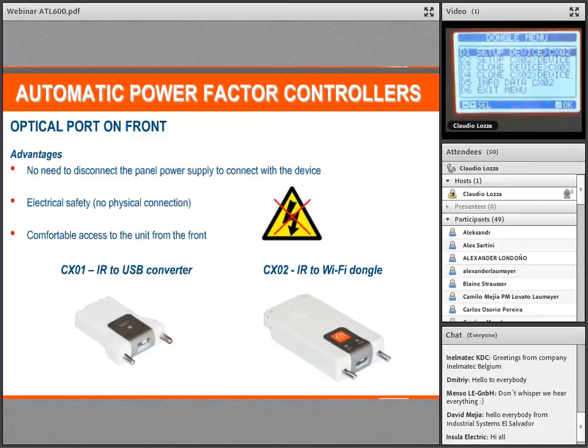Here I can, for example, with the command D1, copy the setup from the device to the CX02. Then with the second command, I can copy the setup from CX02 to the device, and then another big function, the clone function. With the command D3, I can clone the device. What does clone mean? That I copy not only the setup, but the information regarding statistic events too. It's very important when I must change a controller, for example, in case of a wrong situation when I must change the devices. So I can recover the history of the device.